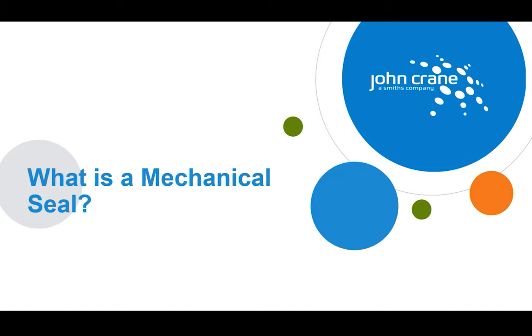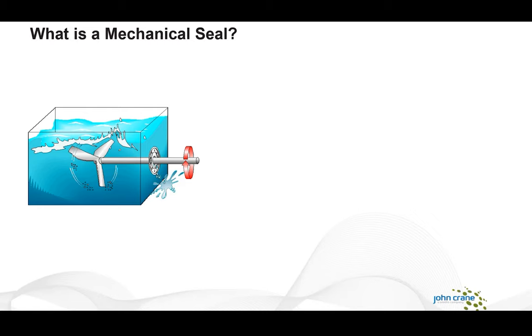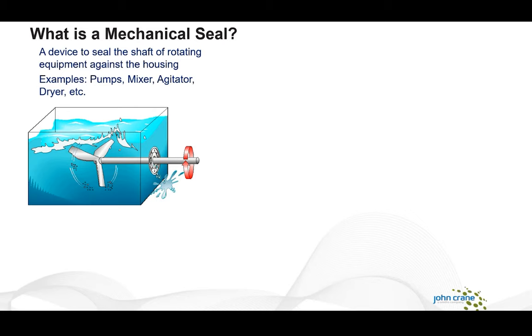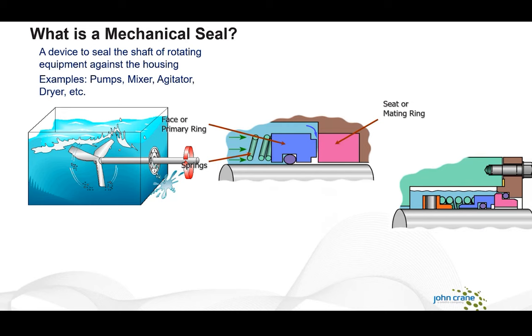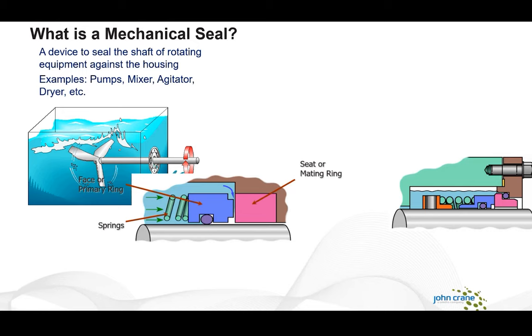So what is a mechanical seal and what is it in relation to a vessel or an agitator? Essentially a mechanical seal is what we call a controlled leakage device. Looking at a tank, we can see the shaft moving through the tank — without a seal this would give rise to a leakage point. The mechanical seal has two faces: one stationary, one rotating. It allows a small amount of leakage across the seal face to lubricate the faces, remove heat, and remove any debris.